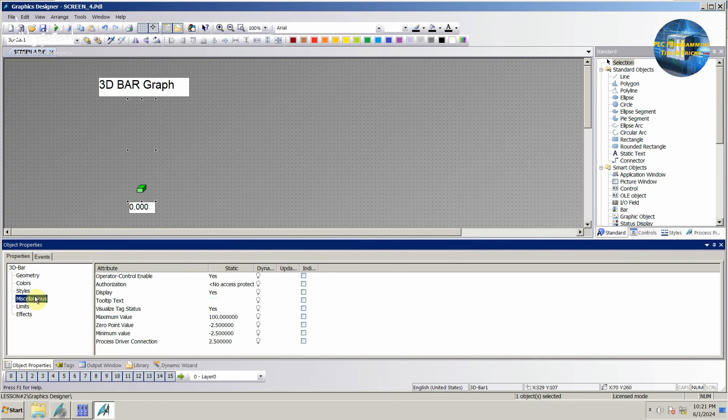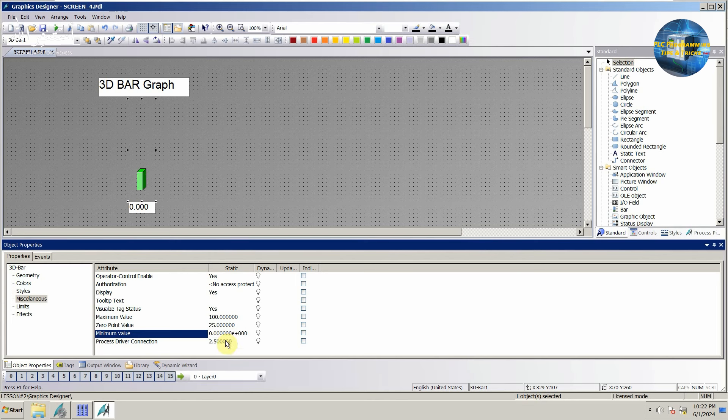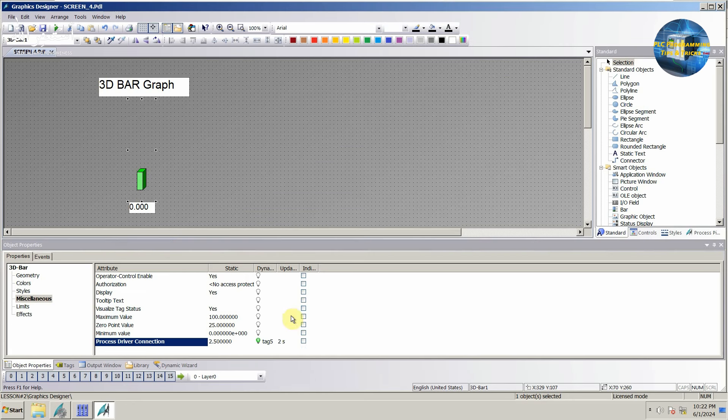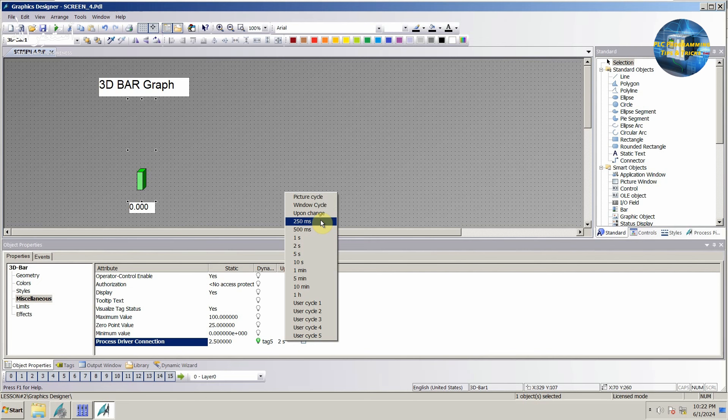Next we will open the miscellaneous menu. We will set the maximum limit as 100 and minimum as 0. Next we will define the process driver connection. We will click on this bulb icon and select tag, and select tag 5 for this bar graph. We can set the update rate for this tag as 250 milliseconds.